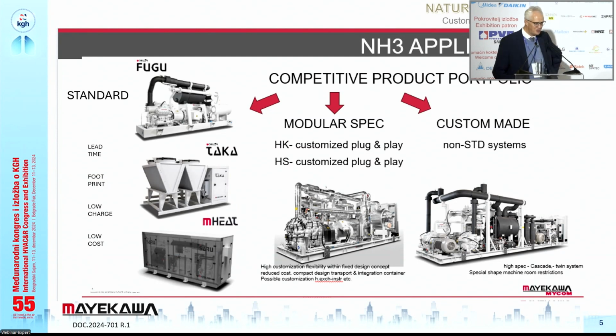We should always have, the target is to have 20 pieces on stock. It's a FUGU, so-called FUGU unit. It is with a water-cooled condenser. The second unit is also a water chiller, but it is smaller.